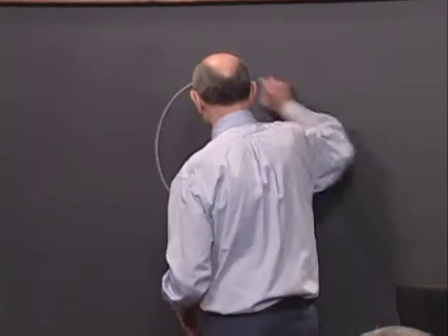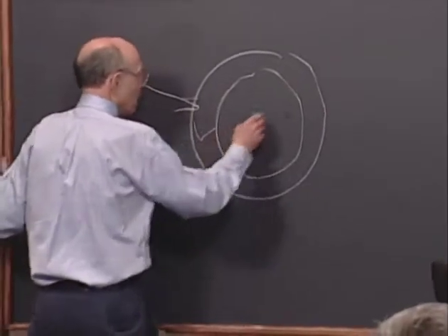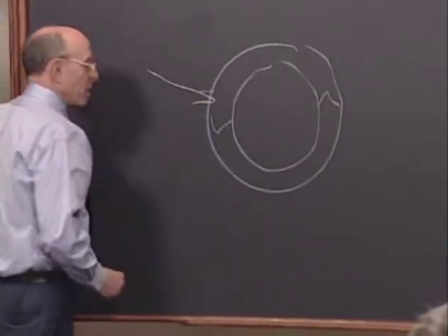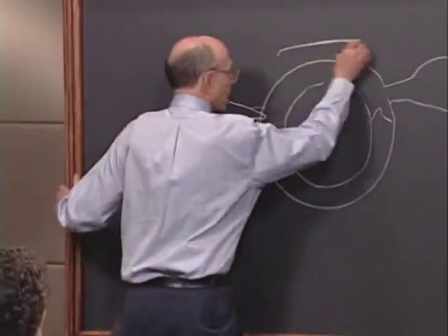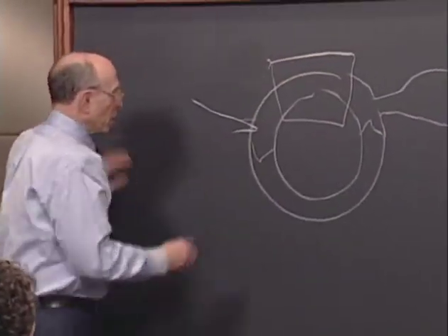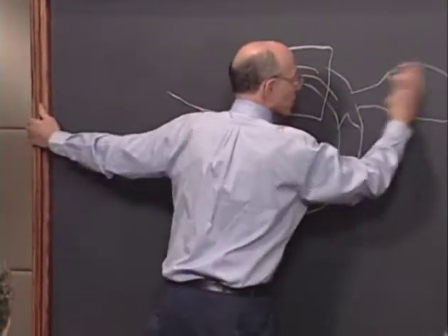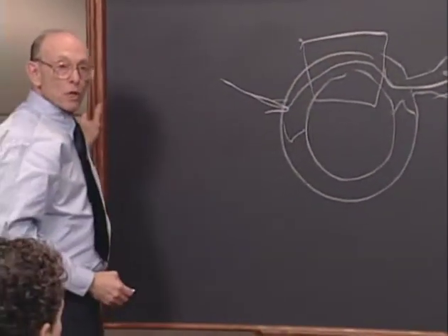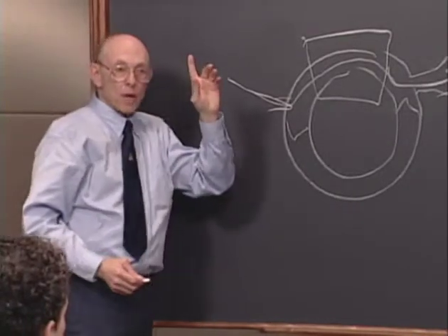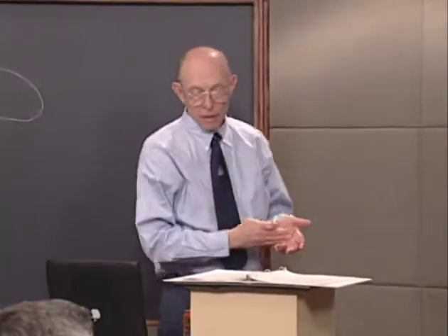And that's because here's our circuit. Here's the gas flow coming in. And there are one-way valves. And here's our reservoir bag over here. And here's our absorbent here. The only way this gas can go back through here is if there's an opening here. Someone took the reservoir bag off and the gas can come out here. That's the only way you can get drying. Leave the flow on and remove the reservoir bag. Then you can get drying. And then you can get the production of carbon monoxide.